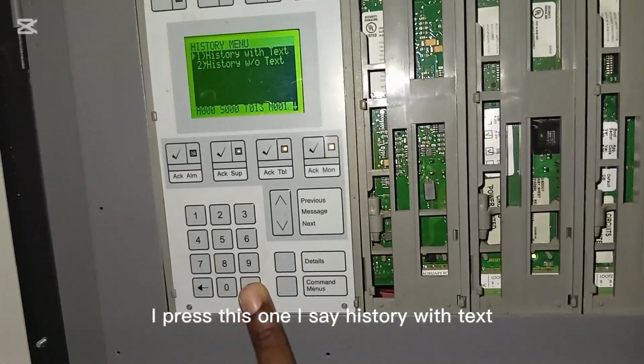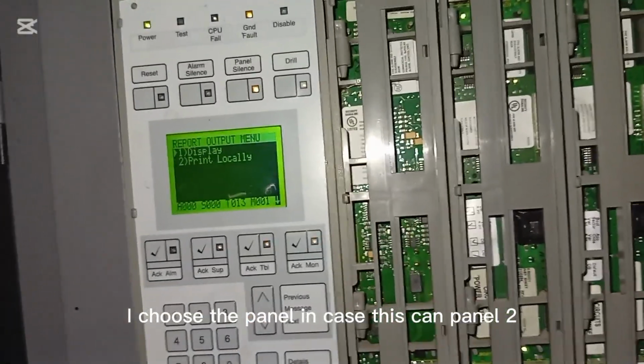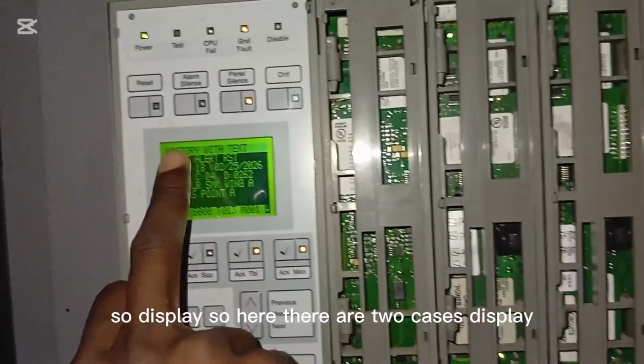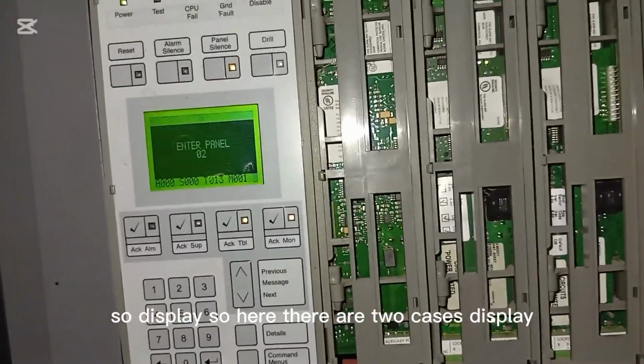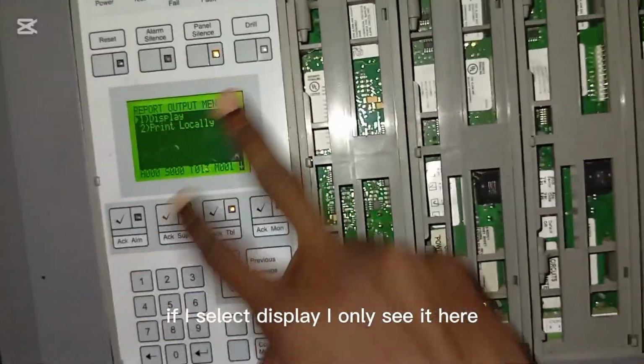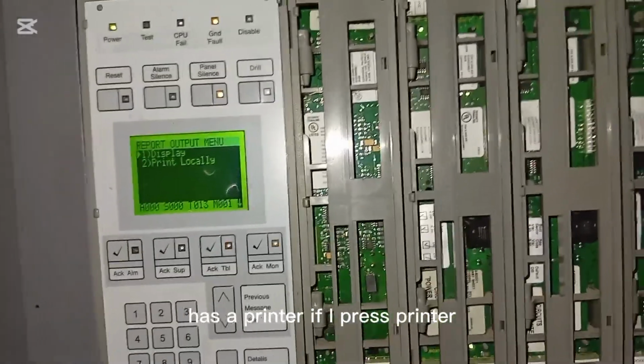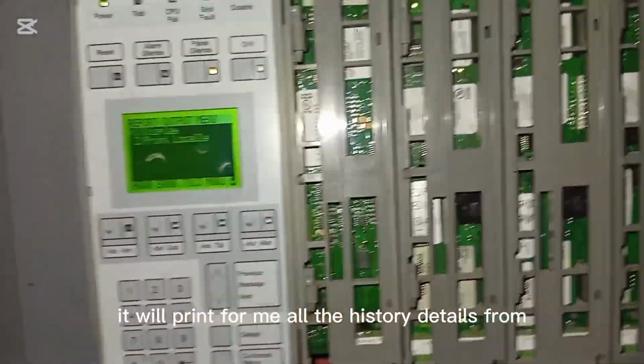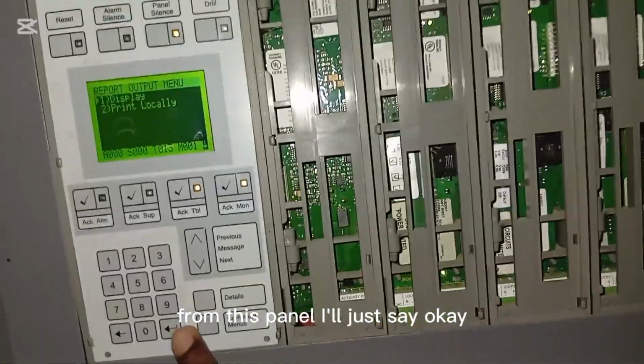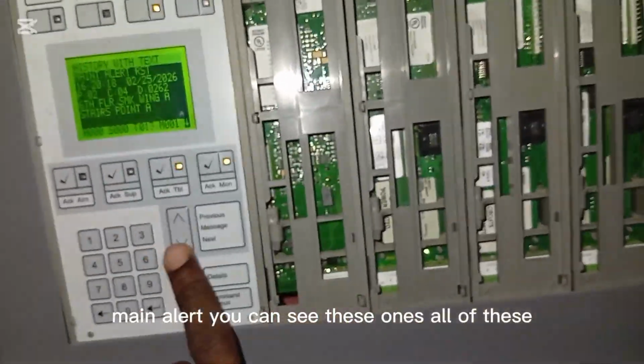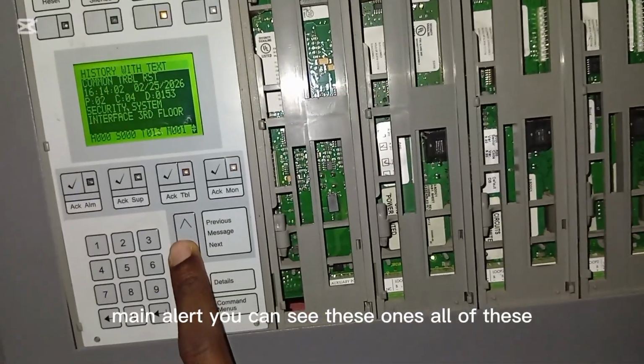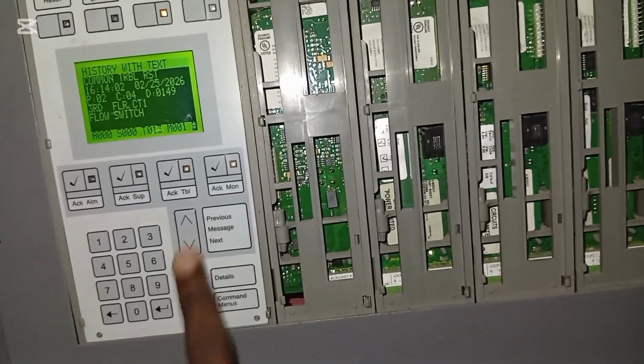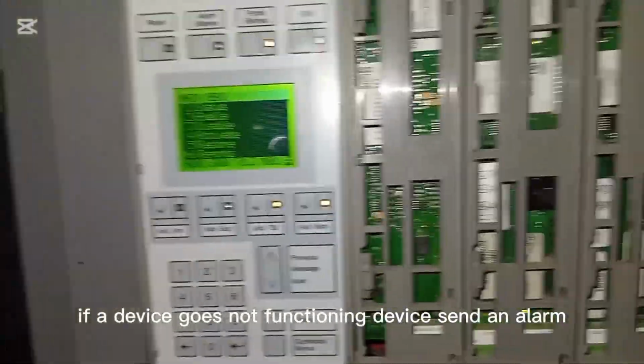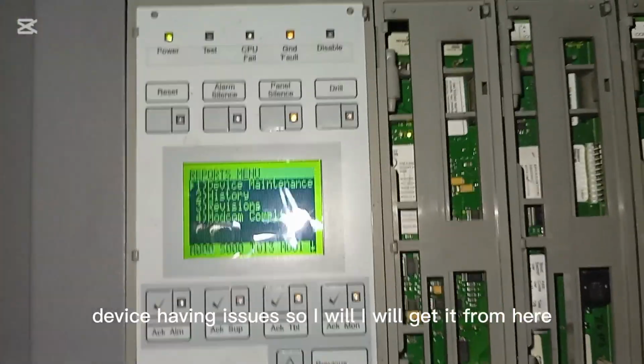I will come to history. I press this one. I say history with text. I choose the panel, in this case panel 2. So display. Here there are two cases. If I select display, I only see it here. But if the system has a printer, if I press printer, it will print all the history details from this panel. I'll just say okay. Main alert, you can see these ones, all of these. So I will get history. If a device stops functioning, sends an alarm, or has issues, I will get it from here.